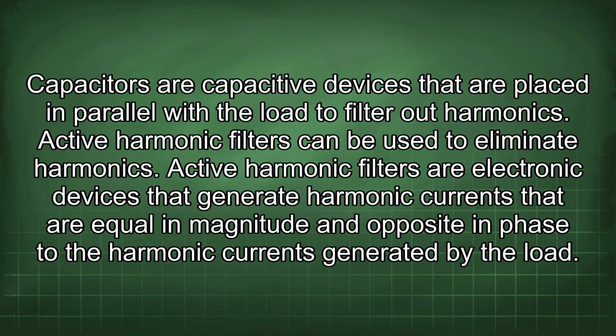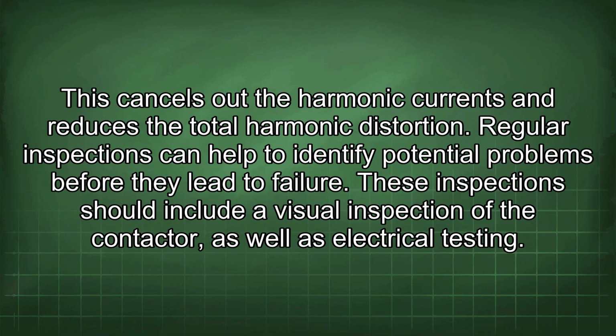Active harmonic filters can be used to eliminate harmonics. Active harmonic filters are electronic devices that generate harmonic currents that are equal in magnitude and opposite in phase to the harmonic currents generated by the load. This cancels out the harmonic currents and reduces the total harmonic distortion.